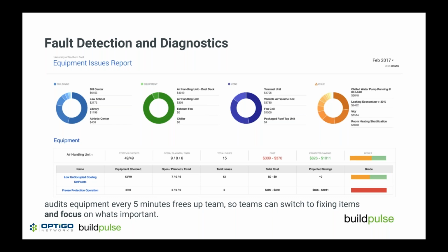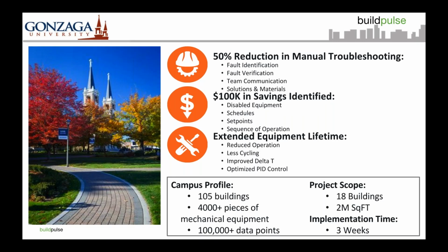Here's just a snapshot of a leaking economizer issue that we found. You can see that it's not happening every day, so if your team just happened to not look at that piece of equipment on that day, they potentially would have missed the issue. Going back to shifting time from manually reviewing data to using aggregate reporting, BuildPulse automatically audits all that equipment every 5 minutes and provides a high-level report so teams can just see their top issues of the week.